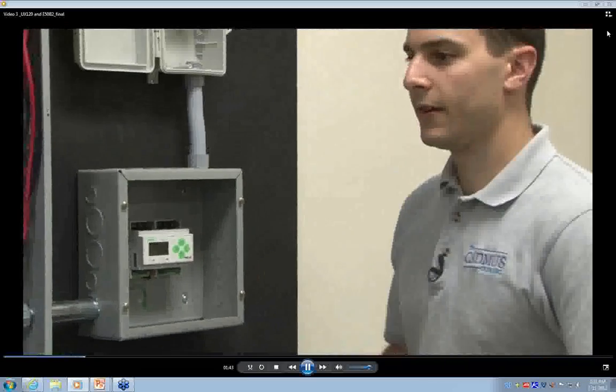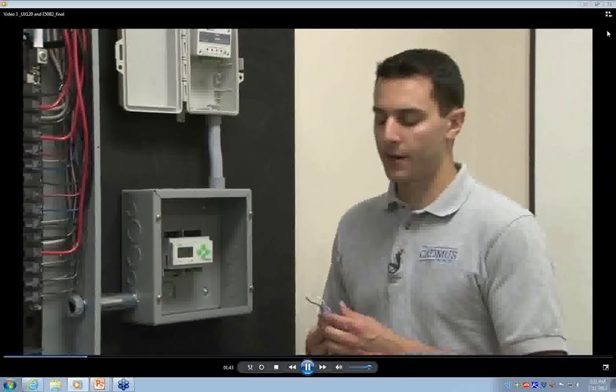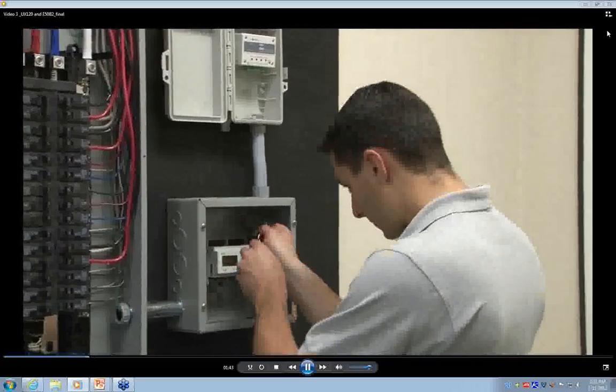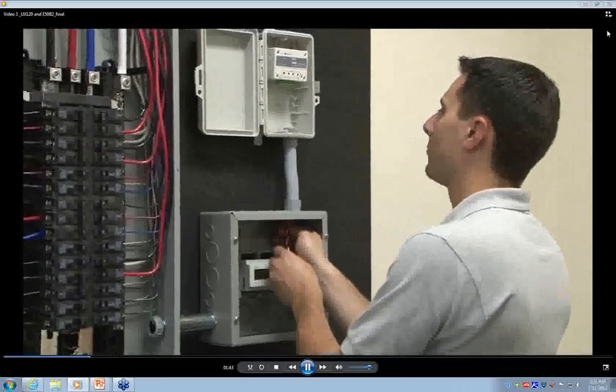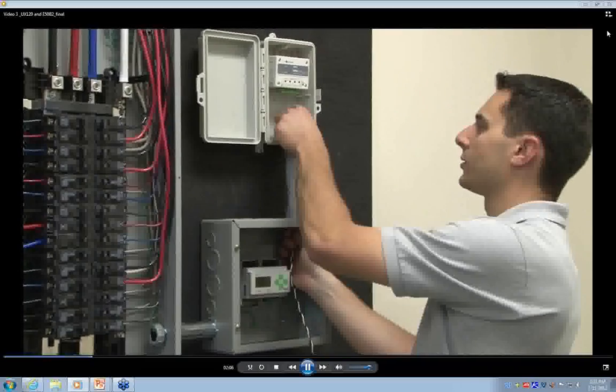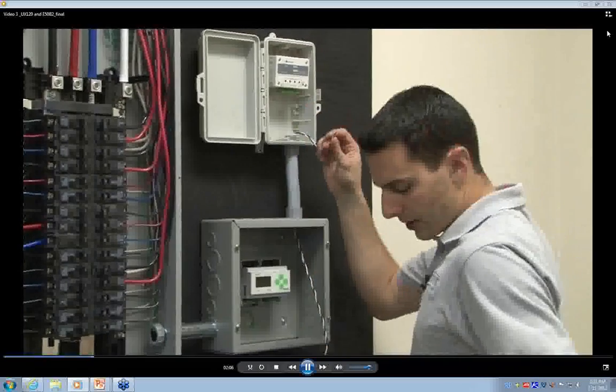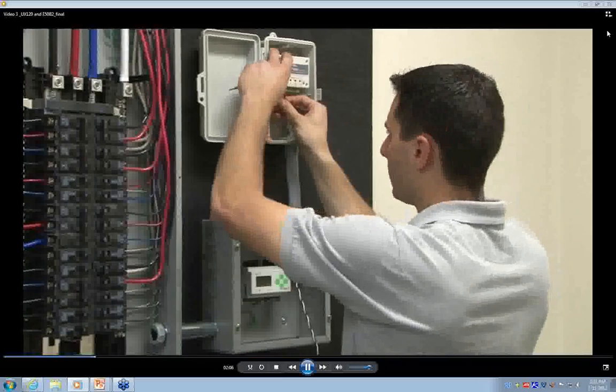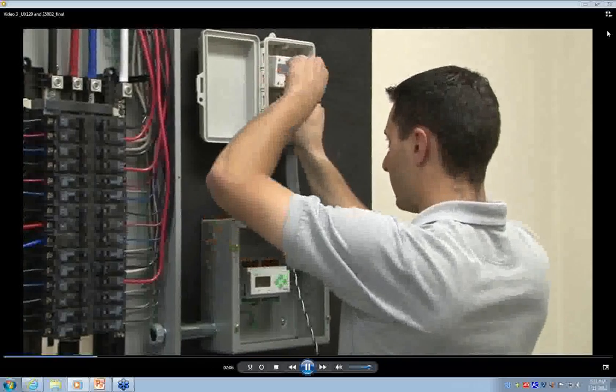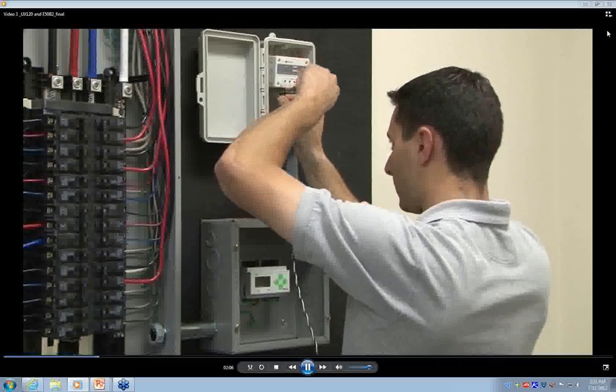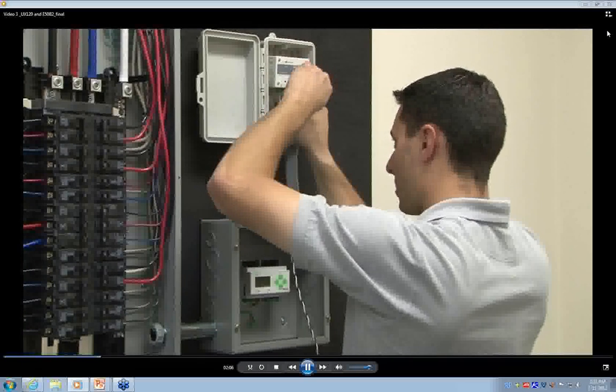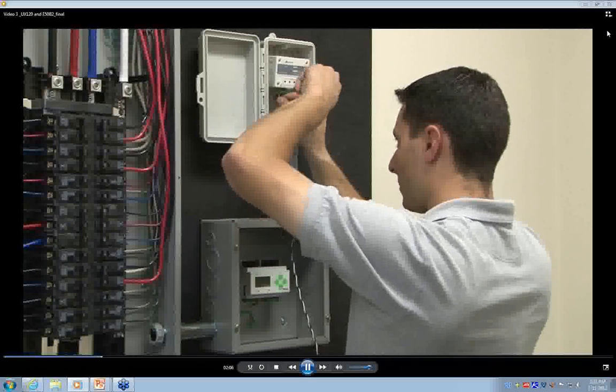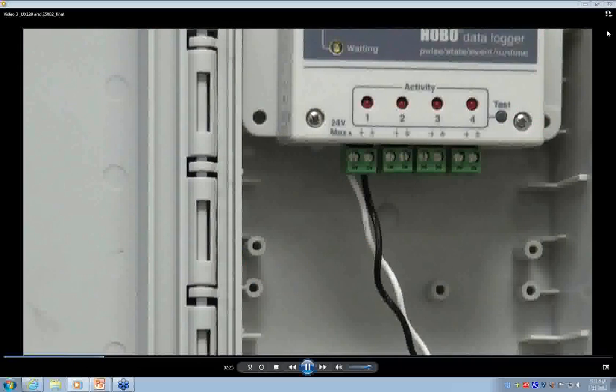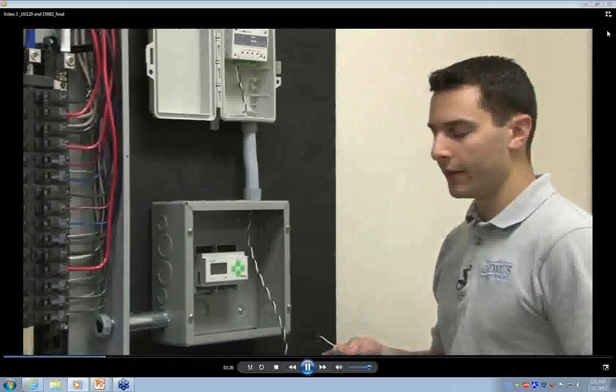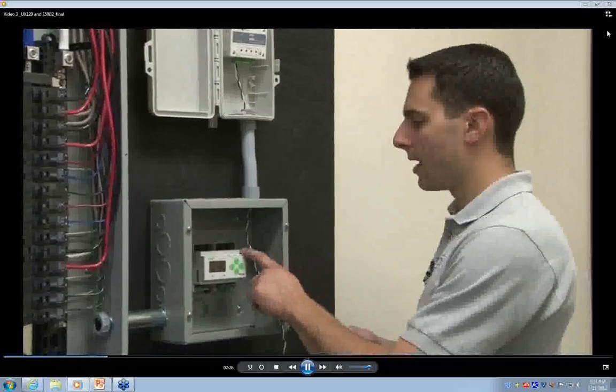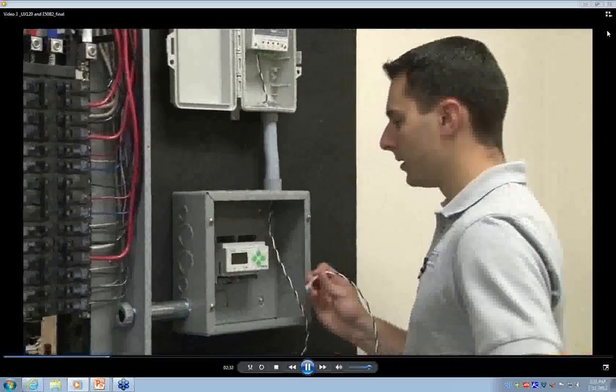For this, we'll use the E50B2 lead set available from Onset. We'll run the black and white conductors up to the UX120. We'll start with channel 1 on the UX120, and we'll connect the channel 1 lead to the volt-amp reactive hour terminal on the E50B2.